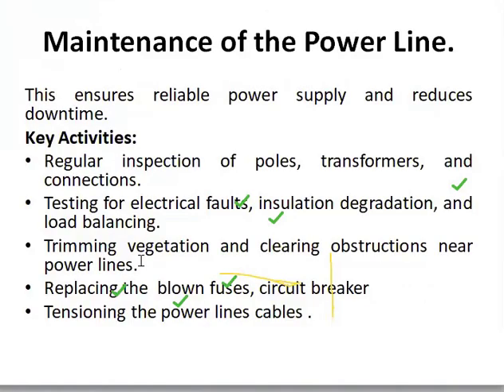So I also do maintenance of the power line, the line that supplies our plant. I always do maintenance on it to ensure that the power is reliable, to reduce downtime. The power that supplies our plant always has some issues in terms of the phases. You find one phase is off or two phases are off, and in a situation where one phase is off, the motor can run, but it runs with some sound. You hear that sound that is not good. Or you find the motor is running but with complications, and it cannot reach its normal speed. So you know that one phase is off.